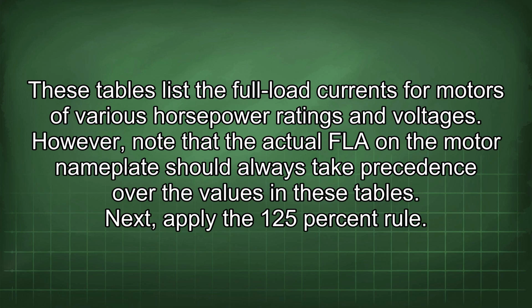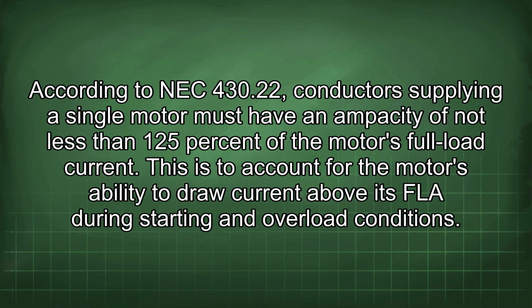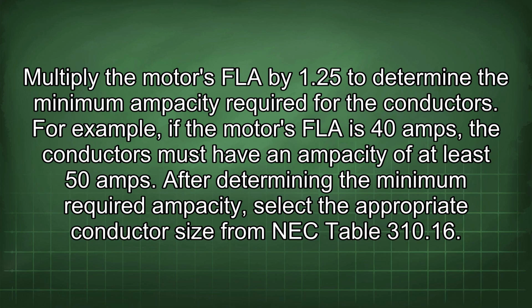Next, apply the 125% rule. According to NEC 430.22, conductors supplying a single motor must have an ampacity of not less than 125% of the motor's full load current. This is to account for the motor's ability to draw current above its FLA during starting and overload conditions. Multiply the motor's FLA by 1.25 to determine the minimum ampacity required for the conductors. For example, if the motor's FLA is 40 amps, the conductors must have an ampacity of at least 50 amps.